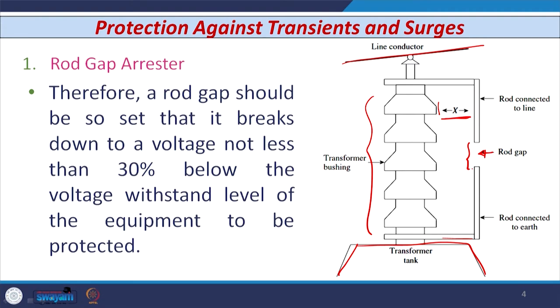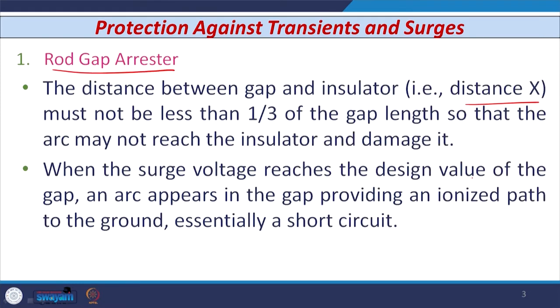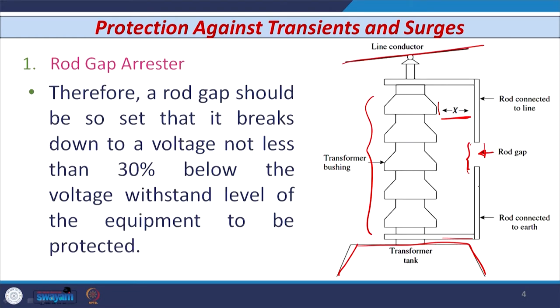A rod gap should be set so that it breaks down at a voltage not less than 30 percent below the voltage withstand level of the equipment to be protected. Whenever the surge voltage reaches the design value, the arc appears in the gap providing an ionized path to the ground — essentially a short circuit. The arc appears across the gap, providing the path, and the bushing is protected.